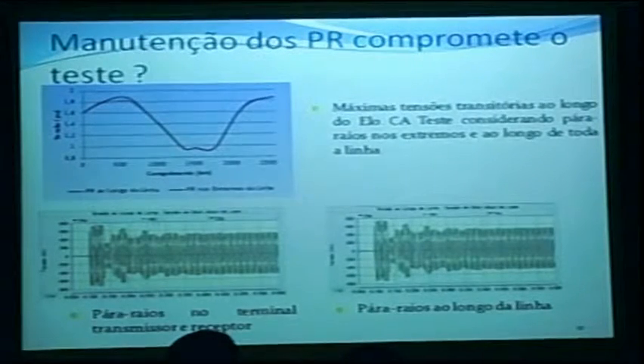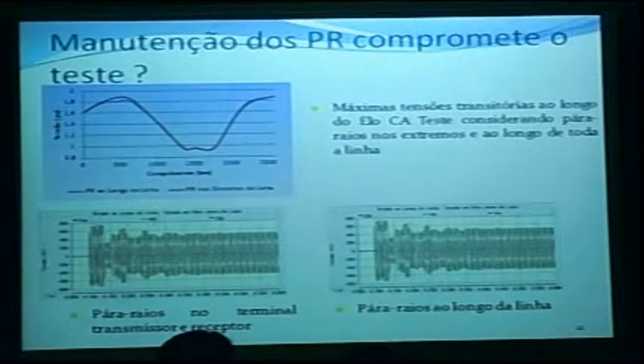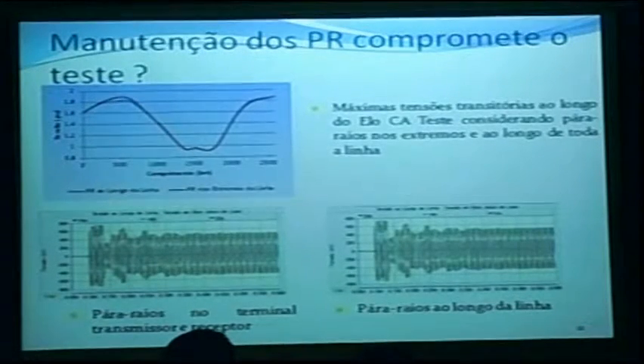This is a maneuver without fault, and it absorbs some of the energy, but this does not compromise the result. You can see that the voltages in the terminals are the same. It's going to absorb some energy here because there's 0.8 or 0.70 something when it starts working. But we can say that keeping the surge arresters throughout the link is not going to compromise it.